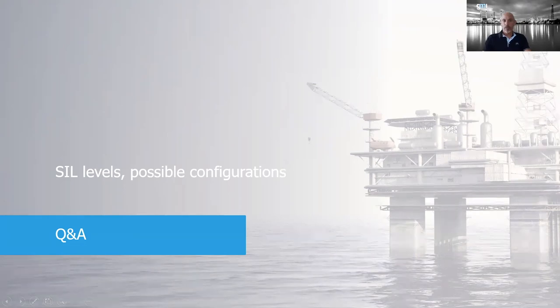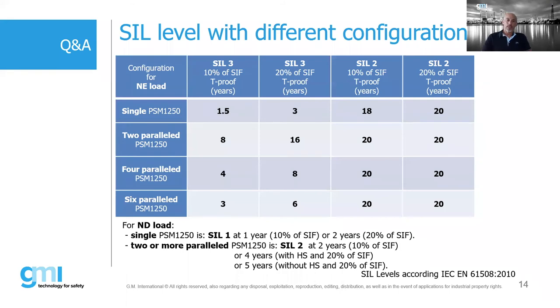So, SIL levels, possible configurations. Looking at our units, we made an example with a normally energized load, just one power supply. If that power supply is participating with 10% of the SIF, the proof test interval in this case is 1.5 years. So every year and a half, I have to test the device again in order to keep the same SIL level.